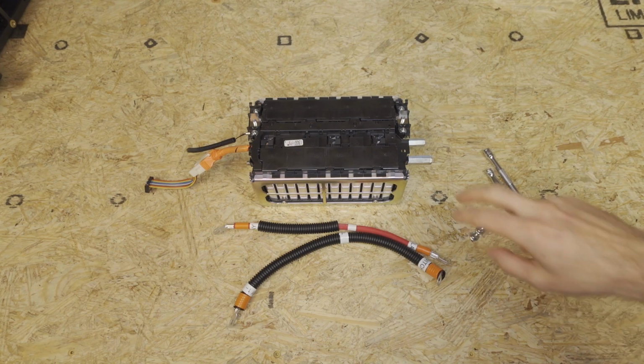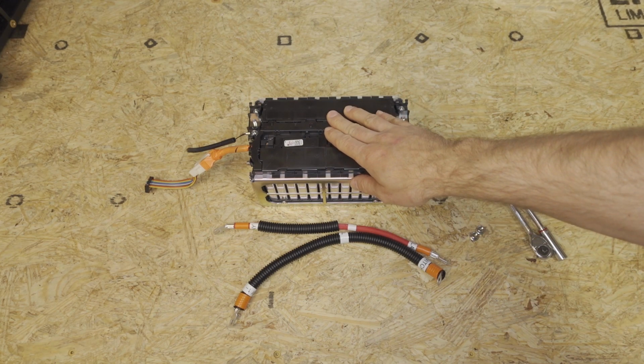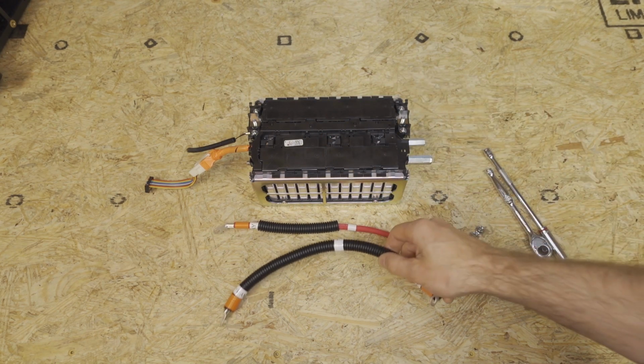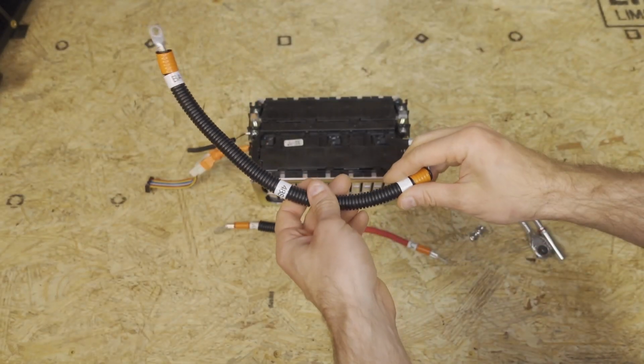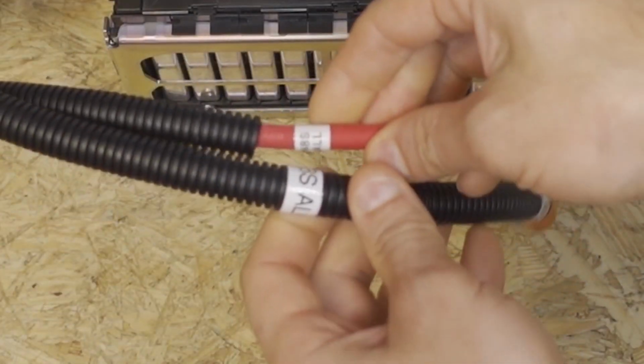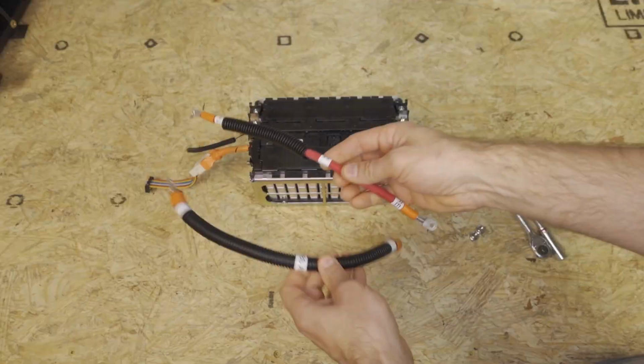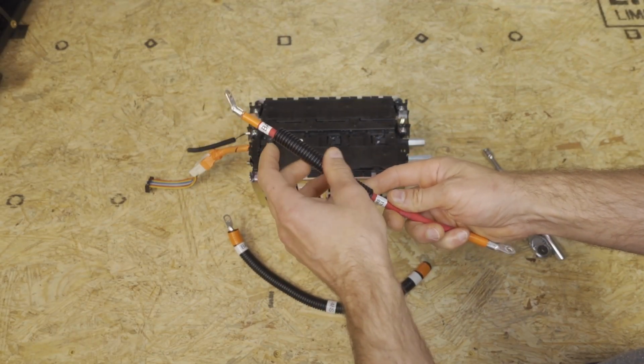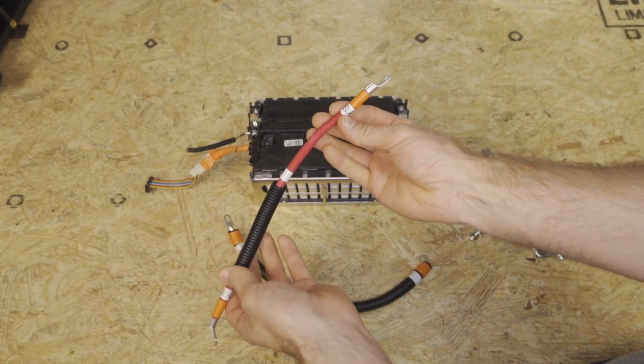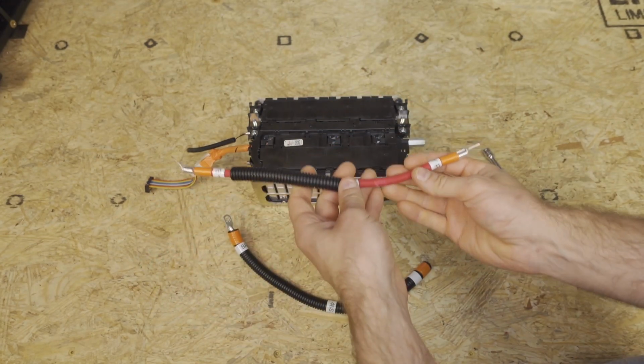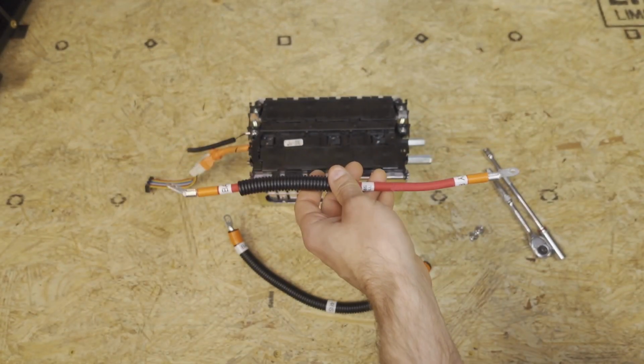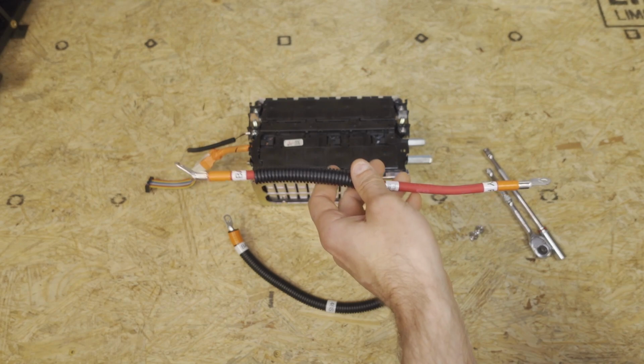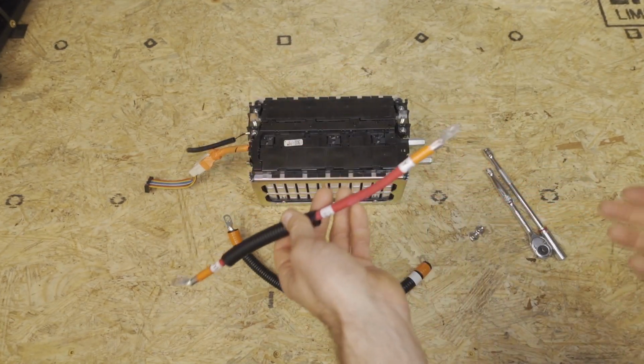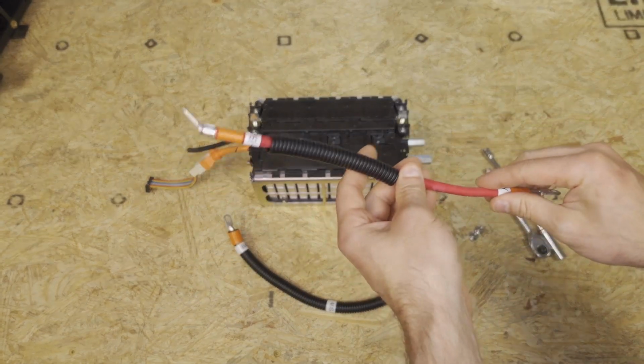Before we install the 12S module inside the battery enclosure, we need to attach the two 48S leads. They have '48S' written on the middle, and the Bay1 positive should go to the relay. Do make sure you verify these, because if you connect these cables incorrectly, you could cause a direct short circuit that could be unfused. So be careful when connecting these cables.